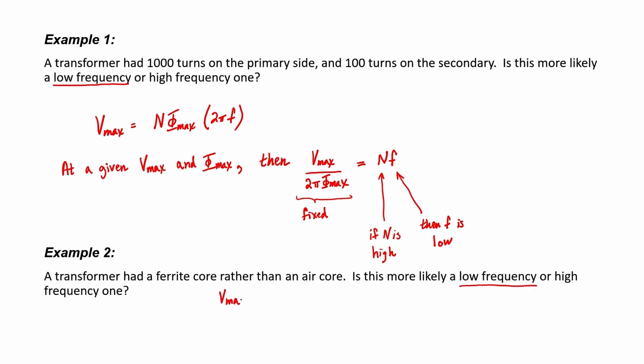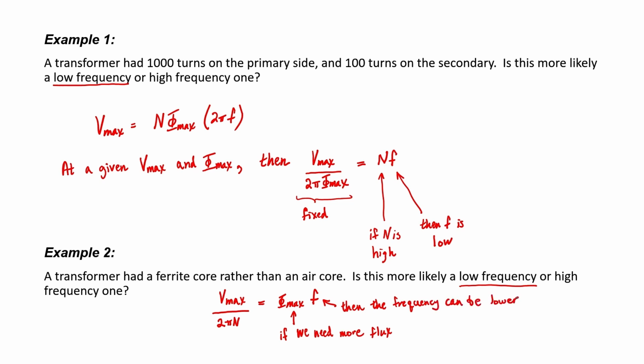If we rearrange this expression a little bit and fix everything on the left-hand side, we can see that the maximum allowable voltage in a transformer is related to the maximum flux times the frequency. I know that iron cores can handle more flux compared to air. So if phi is high, then that transformer was probably designed for low frequencies.